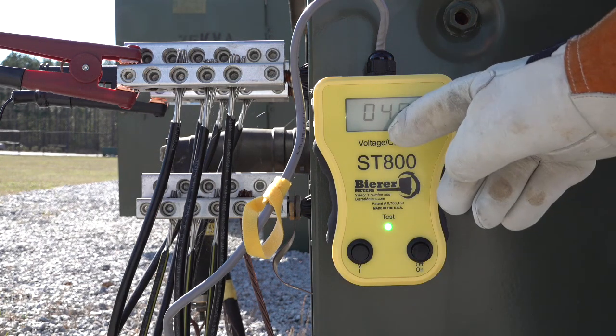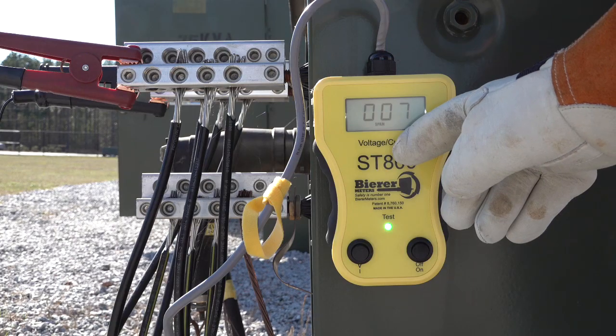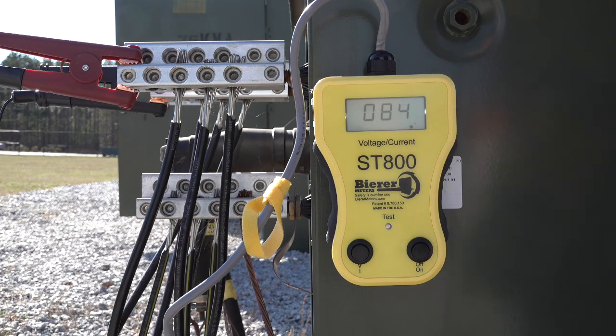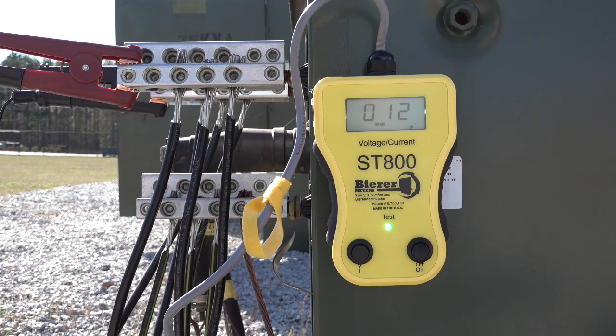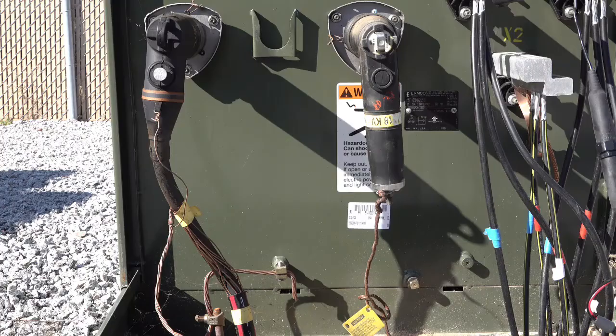With the ST800 now put in the I or current position, we're going to allow it to ramp up to 800 amps before we attempt to verify or identify which primary cable is the source cable feeding this pad mount. Now that the ST800 is pulsing 800 amps, we will attempt to identify which primary cable is the source. As you may have already noticed in our video, the H1B bushing has an arrestor attached to it, so it is obvious which primary cable is feeding this pad mount.